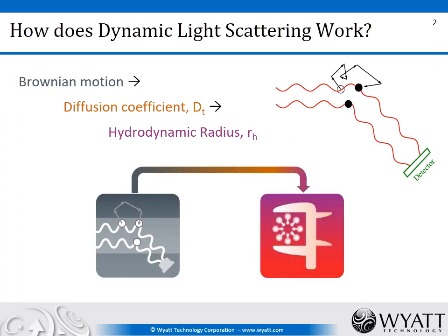Dynamic light scattering is a technique for measuring size of particles in solution or in suspension. It's appropriate for sizes from less than a nanometer and up to several microns. It measures size by utilizing the Brownian motion of the particles in solution. Depending on their size, they will diffuse at different rates. By measuring the diffusion coefficient Dt using light scattering, we can convert that to a hydrodynamic radius Rh, which is a measurement of size.